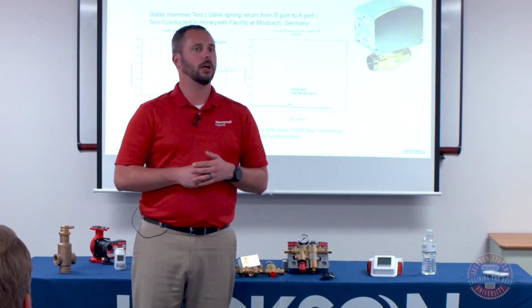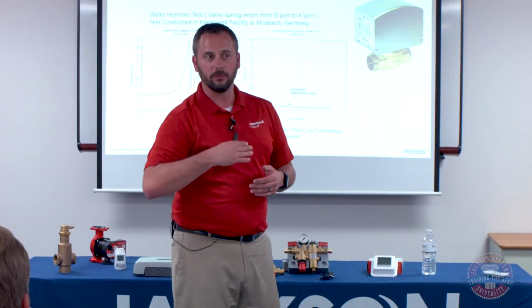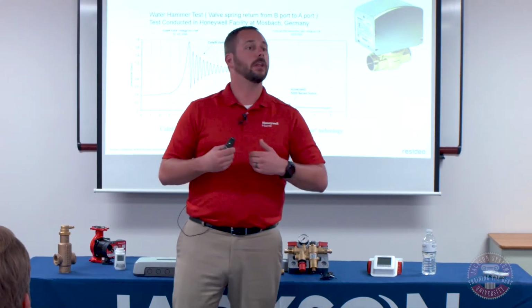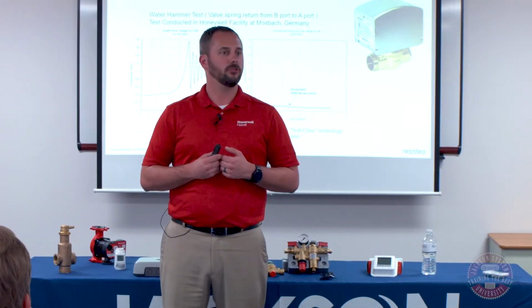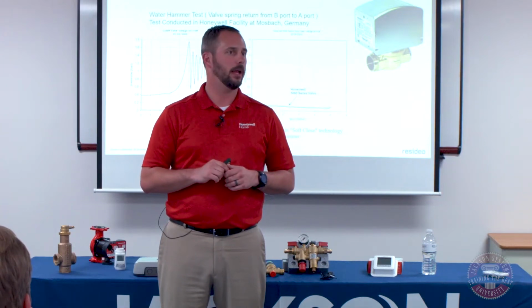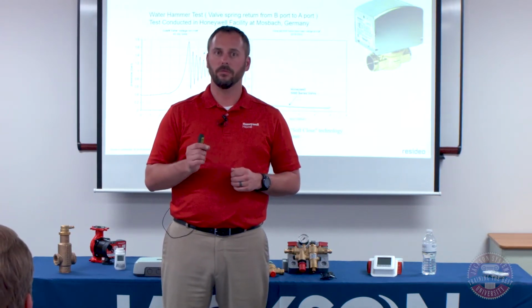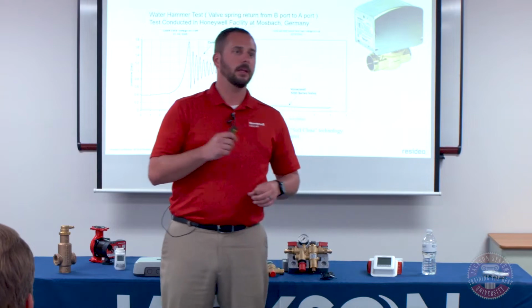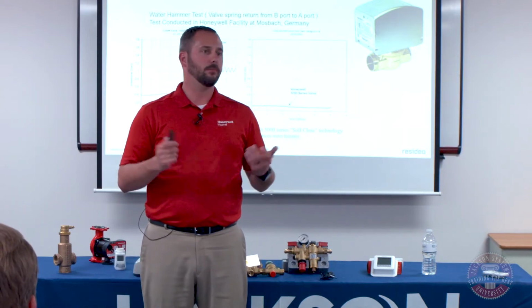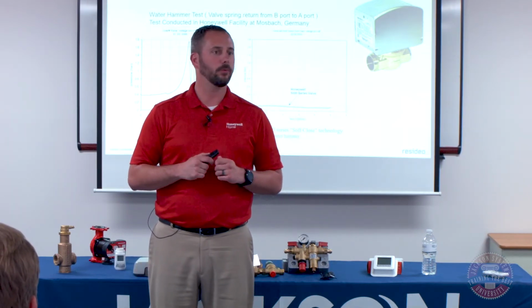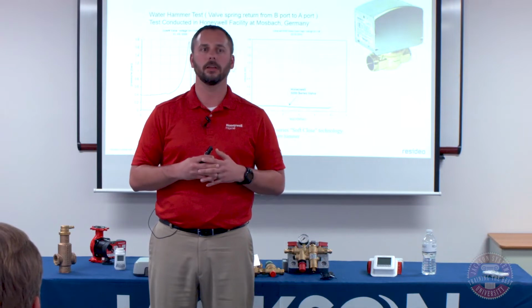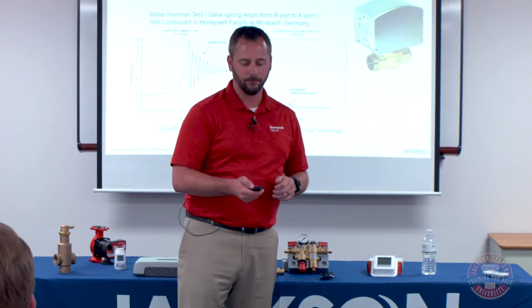So to your customer that said that they've got one that's delivering some water hammer, if it is our valve body, I would suggest throwing in the 5000 series power head. I'm very confident that that will fix the problem. If it's not our valve, you could probably even start with our 1000 series. It would probably do the job, but 5000 is very effective at controlling water hammer.